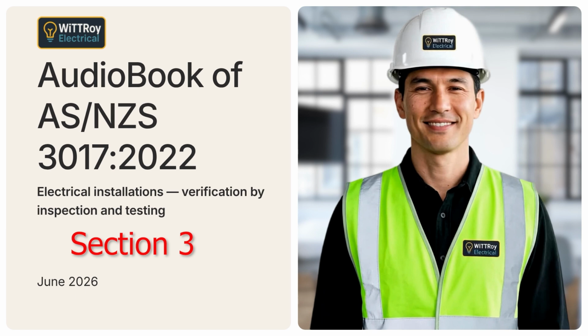The risk assessment should also identify what equipment is needed for the inspection. This may include a torch, access equipment, barriers, signs, test equipment, or other tools needed to inspect safely. The risk assessment should also consider safe access. This is important because visual inspection may involve switchboards, roof spaces, ladders, ceiling areas, underfloor areas, plant rooms, outdoor areas, or other locations where access may create extra risk. ASNZS 4836 gives further guidance for safe work. In simple terms, visual inspection is not just looking. You still need to plan the work safely, choose suitable PPE, use suitable equipment, and make sure the work area can be accessed safely.